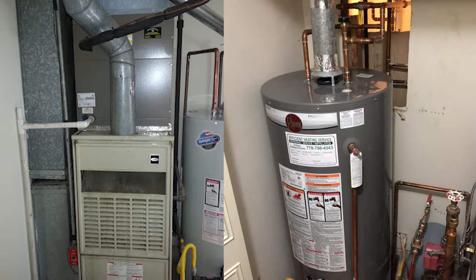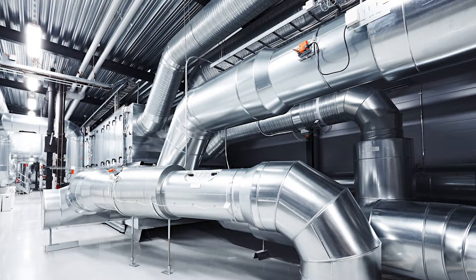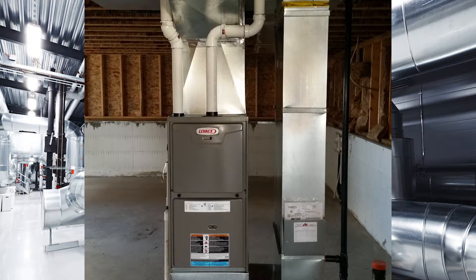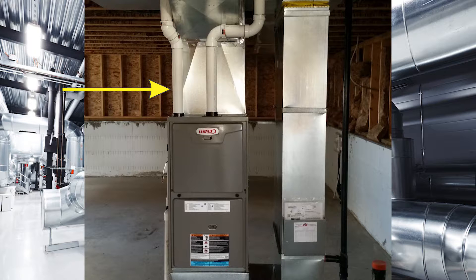Category one natural draft appliances are antique in nature and they are being phased out. We will see them in older buildings and they still exist quite widely with hot water tank installations today. The most common type of installation today is the category four or high-efficient furnace. These are generally direct vent, meaning they have their own exhaust vent and their own air intake vent, so they don't require air supply like we're going to talk about in this video. All that venting is installed by the official manufacturer's instructions.